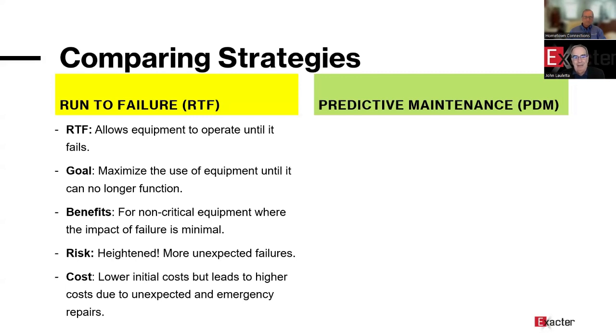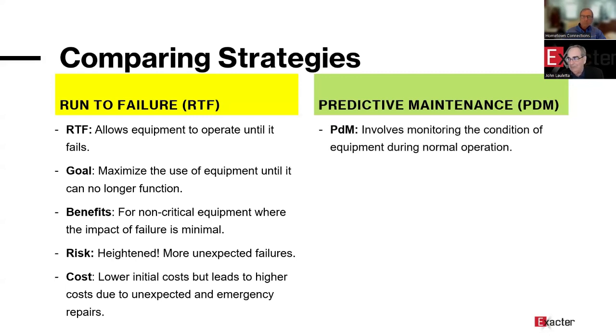But let's now look at the other side of this, and let's talk about predictive maintenance. And predictive maintenance has a meaning that's defined by its name. It means rather than waiting for a failure, we're going to predict that a failure could occur, and if the failure result would be important, we may want to do something about it before it occurs. Now, the difficult part of predictive maintenance is you have to know the condition of all the equipment that you have in your predictive maintenance program. Those billions of devices, it may be tens of thousands to a million in your company, all the insulators, all the cross-arm connections, all the lightning arrestors, disconnects, fuse cutouts, all that equipment has to be evaluated for its performance while it's running.